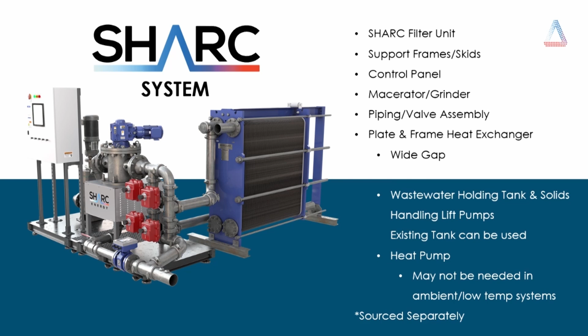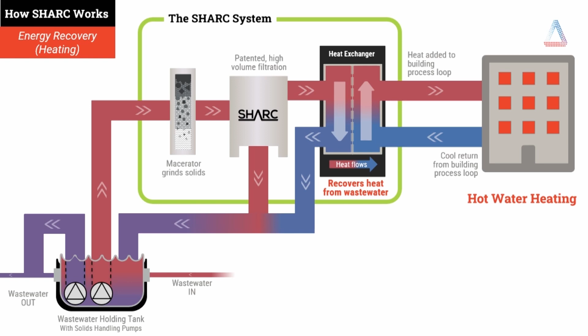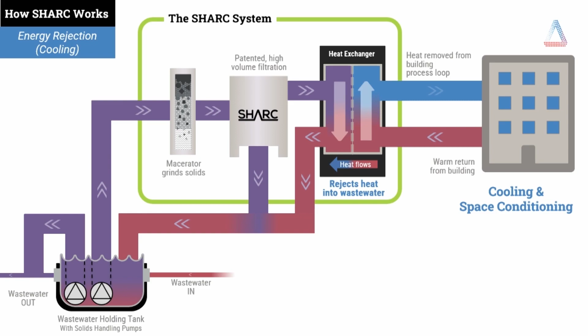and then we can just basically cycle it back out to city sewer. And because the Sharc can operate in both directions, we can do heating and cooling just by reversing the flow. So in this diagram, you see that we're taking energy from the sewer and pushing it through the Sharc and into the building, taking the cold return through the Sharc and down out to city sewer. And then by reversing the flow, we're now able to take rejected heat from the building and now dump it into city sewer.